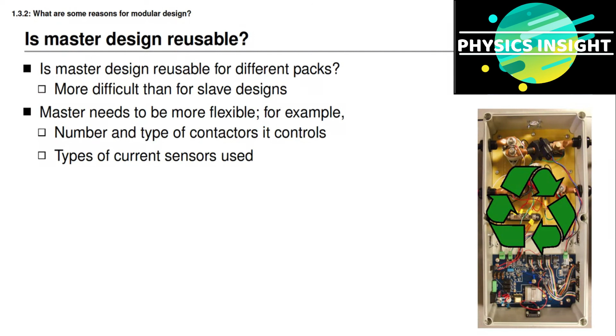There may also be different types of thermal management system. So it's possible to reuse the design of a master battery management system, but this can only be accomplished by incorporating a lot of flexibility, using additional analog and digital inputs and outputs that might be required in a special purpose design.